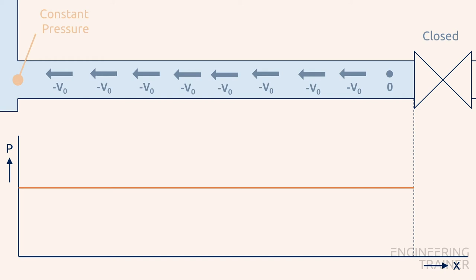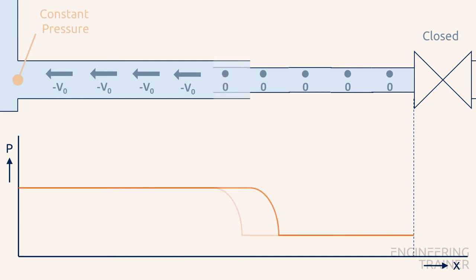Now the momentum of the water in the pipe doesn't tend to compress the water close to the valve but it tends to expand it. So no local pressure increase is created but a local pressure drop. As a result there's again a local pressure gradient close to the valve that interacts with its neighboring sections in a similar way causing the pressure wave to move through the line again.